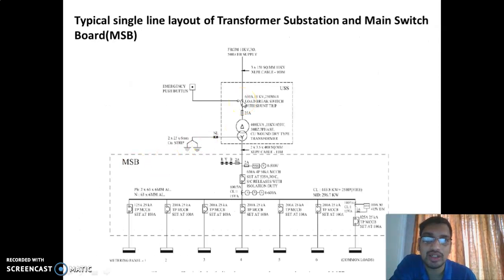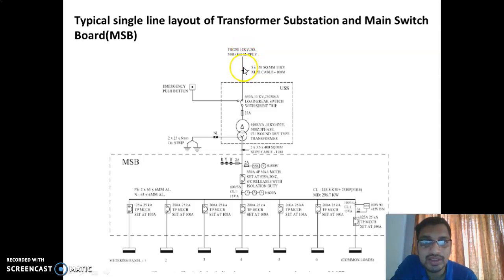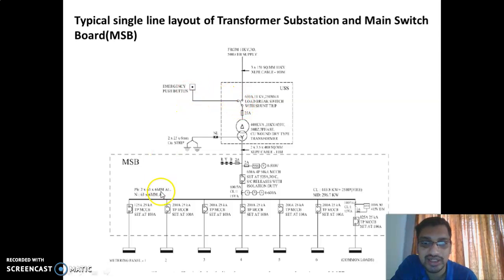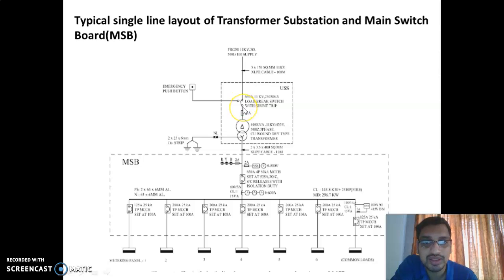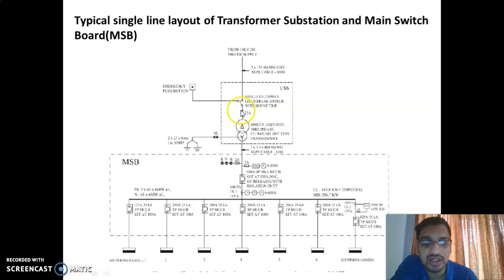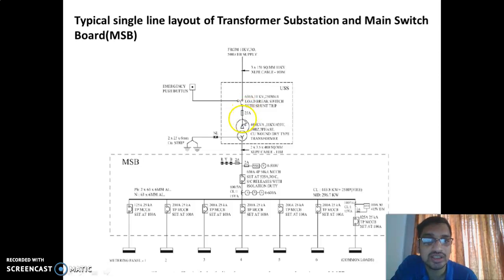This is the typical layout of a medium type of industry. The HT connection is received from the electricity board at 11 kV supply, then connected via a primary XLPE cable of 150 sq mm. An emergency switch is connected so that in case of accidents or fire, we can switch it off to interrupt the complete supply. After that, there is a load break switch, then a fuse whose rating depends upon the rated current in the primary side of the transformer.